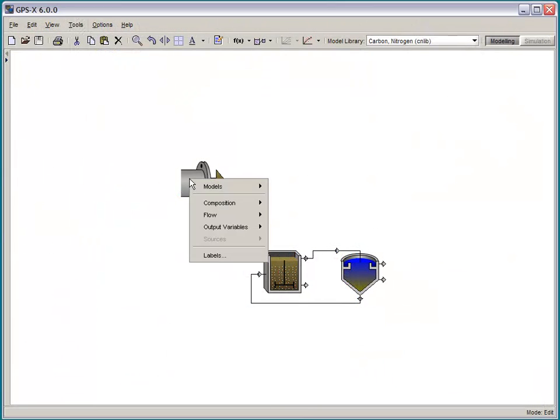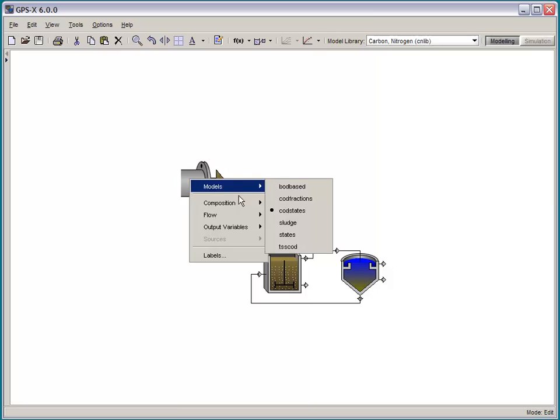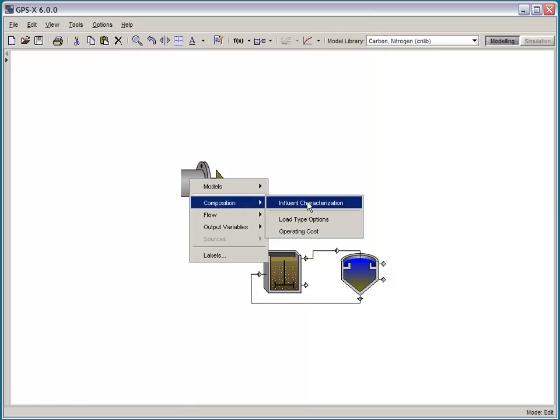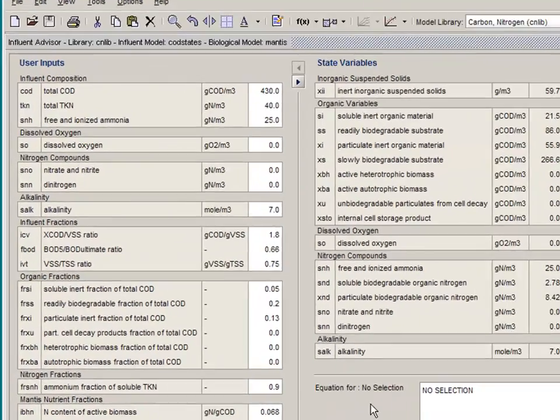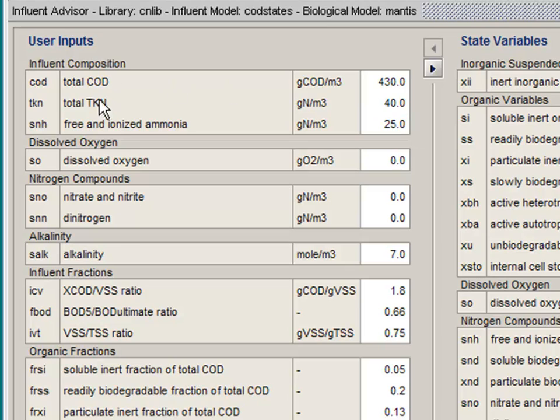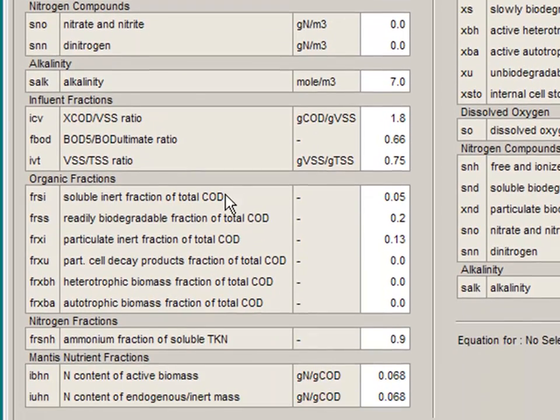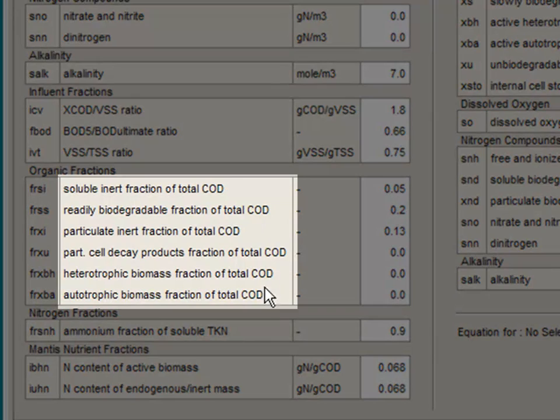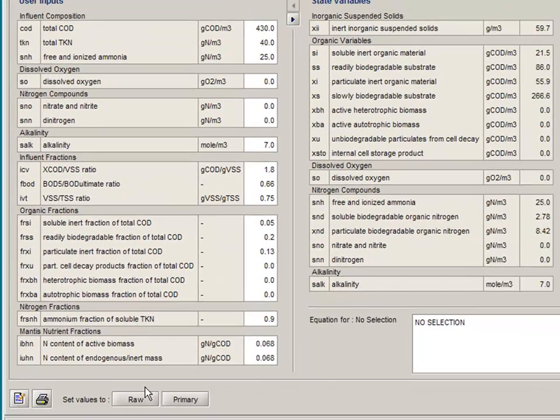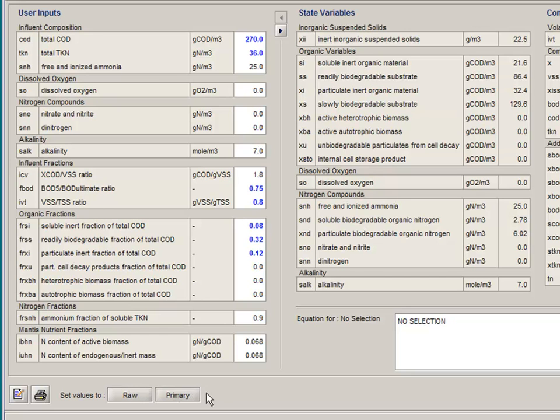We have also added a new influent model called COD states. The idea behind this model is to allow for influent characterization in terms of total COD. So you enter total COD, total TKN, and ammonia. And then the inert and readily biodegradable and so forth. The fractions are of total COD in this case. And we have prepared the usual two sets of default influent fractionations.